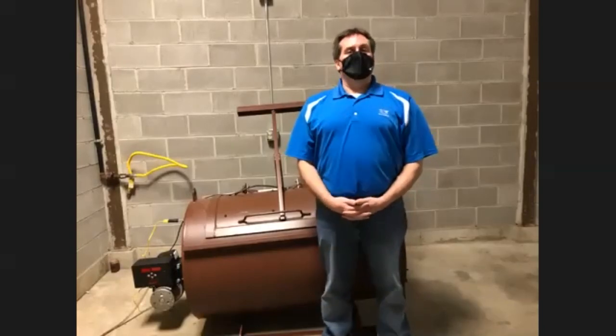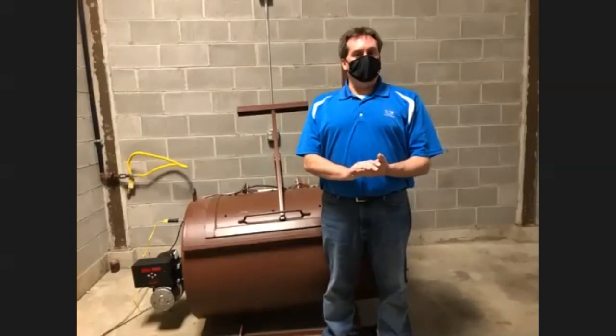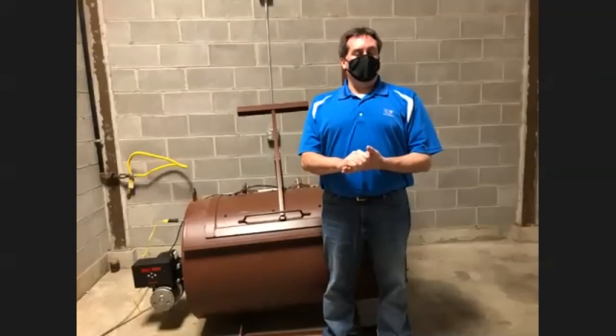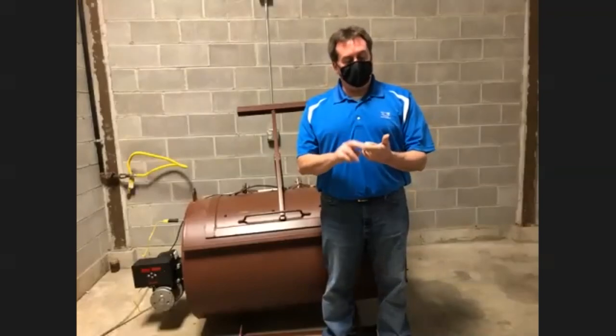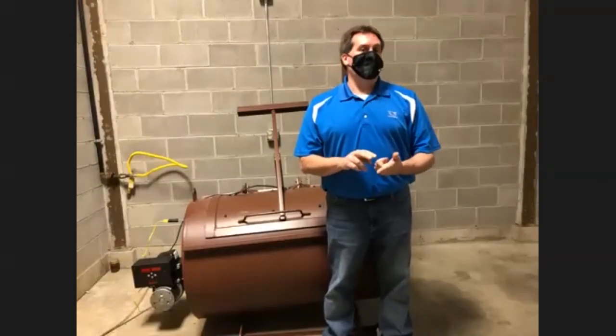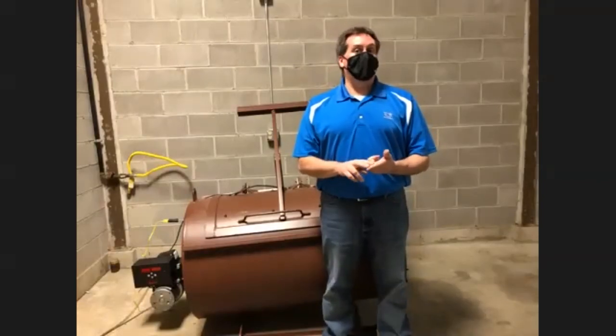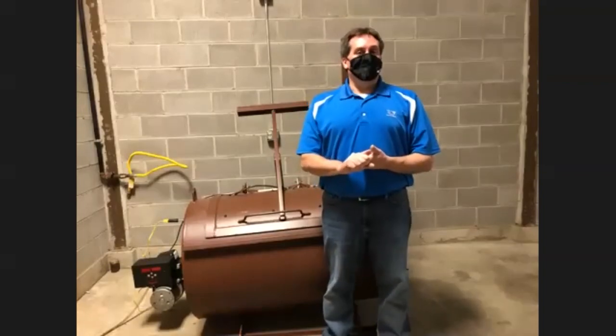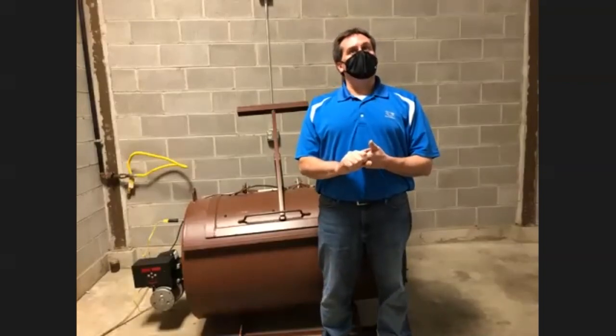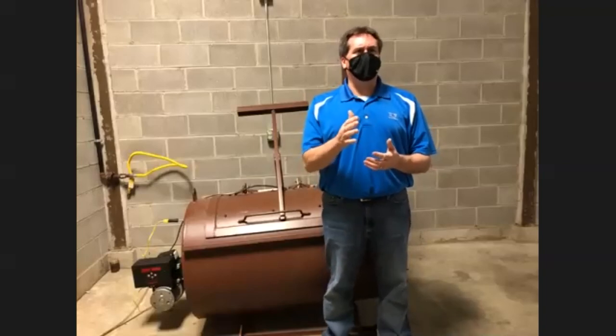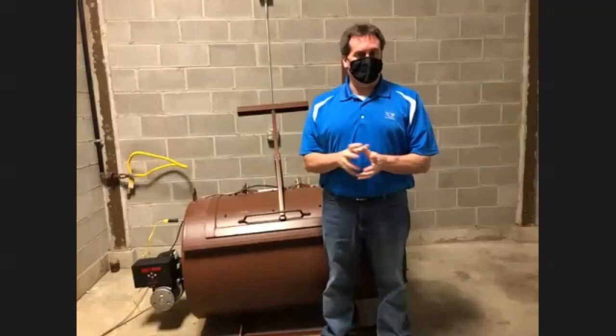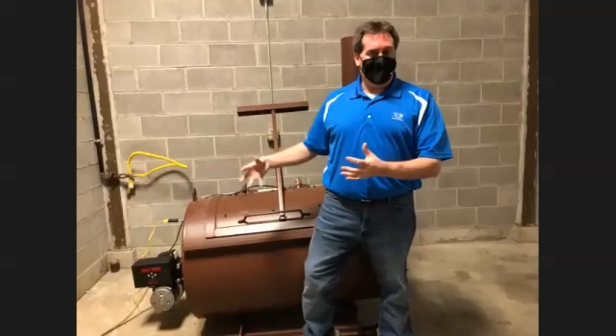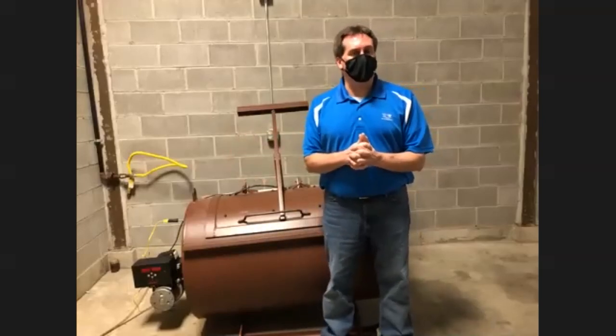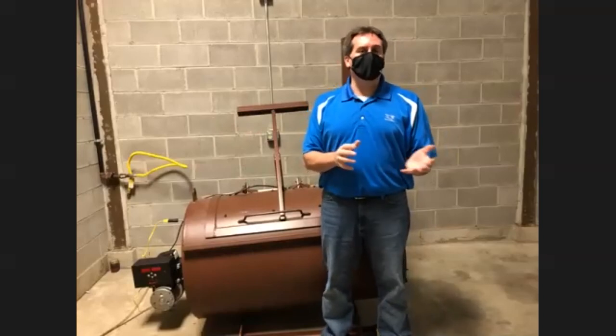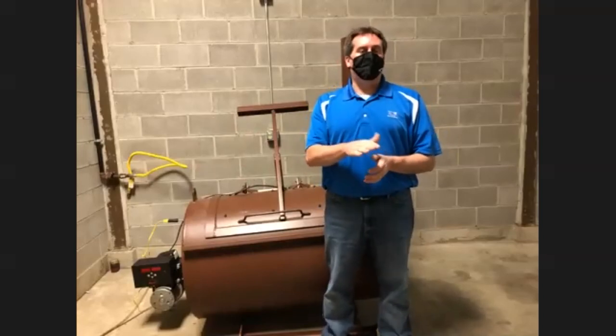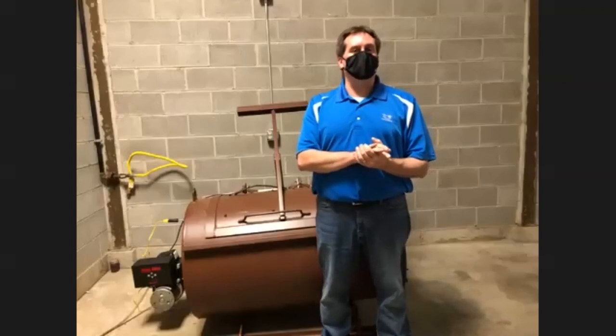That definitely indicates you have a low voltage supply issue, and you definitely want to verify. You could have an improperly sized wire going to it. You may have the wrong length. You may not have the proper breaker to it. You need to stay above, I think it's right around 119 or higher, is what you need. Since they pull so much power igniting, it is a little touchy on that, so you need to make sure you have the proper supply too. 118 is probably just on that borderline, just barely enough to do it properly.